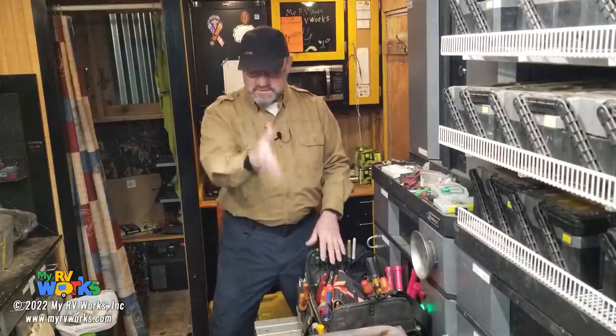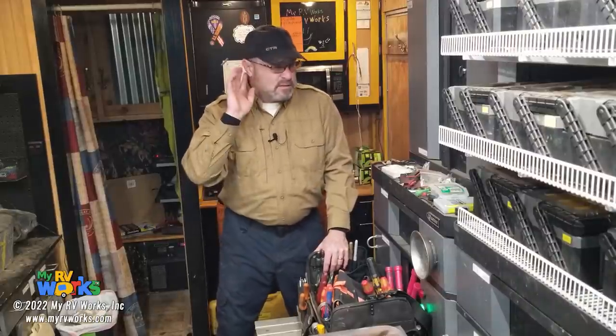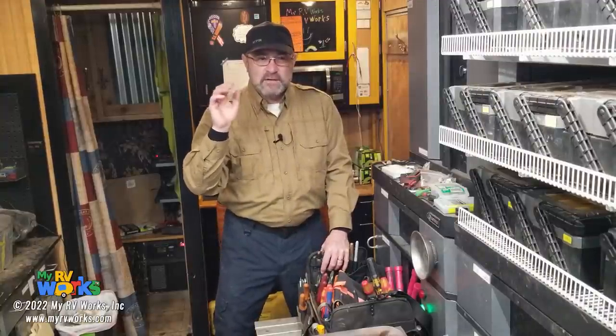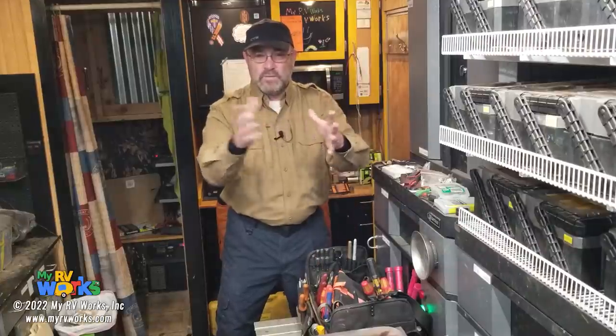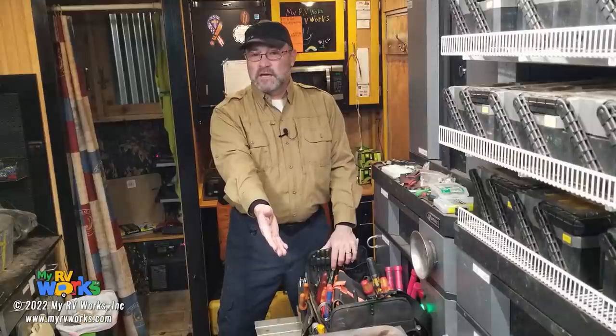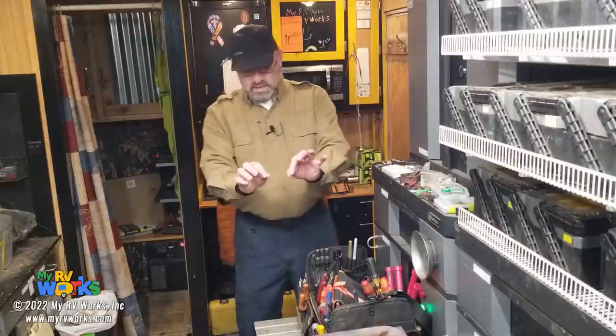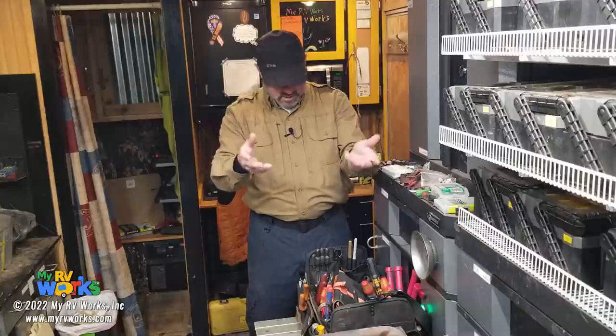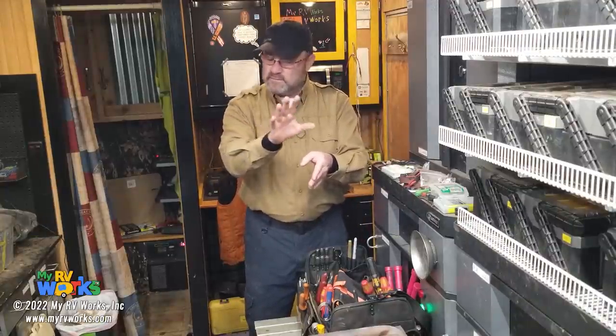It didn't do it right away on this particular furnace. It took maybe 5 to 10 minutes somewhere in there. And if you're here, you can actually get close to the exhaust on the outside and you could hear the click, tick. What you're hearing is the gas solenoid engaging and disengaging, opening and closing the gas valve. And so it's like, gee, it's not the high temperature switch. It wasn't that. So then you take your meter and you watch the current going through this. It's just a continuity check. You put your meter in continuity mode. And when the furnace was doing this cycling on and off, the switch wasn't turning on and off.